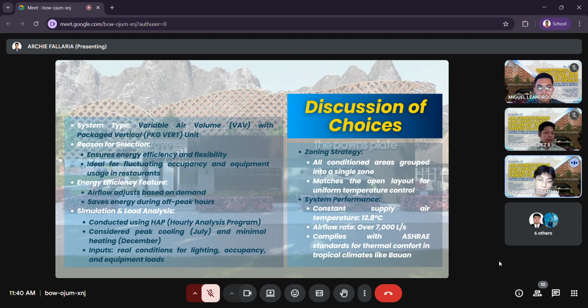Detailed simulations using HAP accounted for peak cooling in July and the minimal heating in December, using accurate inputs for lighting, occupancy, and equipment loads to reflect real conditions. All conditioned spaces were grouped into a single zone for simplicity, matching the open layout and ensuring uniform temperature control. The system maintains a constant supply air temperature of 12.8 degrees Celsius and delivers over 7,000 liters per second of airflow, following ASHRAE standards for comfort in tropical climates.